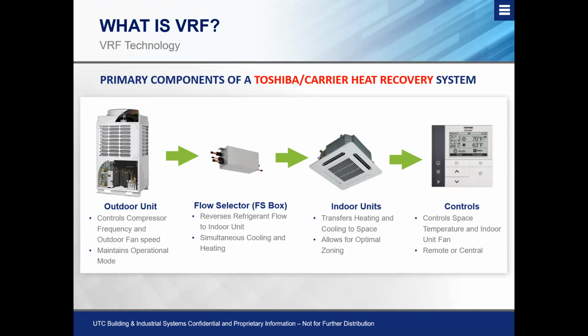Now, if it's a heat recovery, you'll feed into a flow selector box. If it's not heat recovery, you'll flow directly into the building. So as a rule of thumb, Toshiba carrier in the 3-pipe style systems is what I prefer them to be referred to as, just to eliminate confusion. The quote-unquote 2-pipe styles are referred to as carrier. And of course, differentiate whether you need heat pump or whether you need heat recovery.